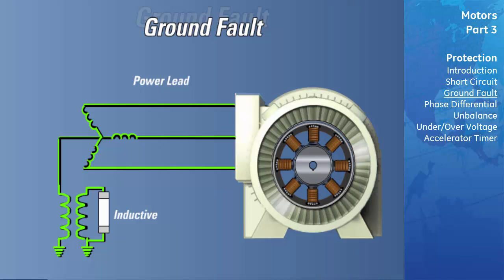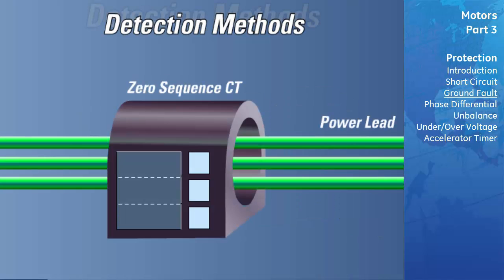There are several ways by which a ground fault can be detected. The most desirable method is to use the zero sequence CT approach. This is considered the best method of ground fault detection due to its sensitivity and inherent noise immunity. All phase conductors are passed through the window of the same CT, referred to as the zero sequence CT. Under normal circumstances, the three-phase currents will sum to zero, resulting in an output of zero from the zero sequence CT secondary. If one of the motor's phases were to short to ground, the sum of the phase currents would no longer equal zero, causing a current to flow in the secondary of the zero sequence CT. This current would be detected by the relay as a ground fault.